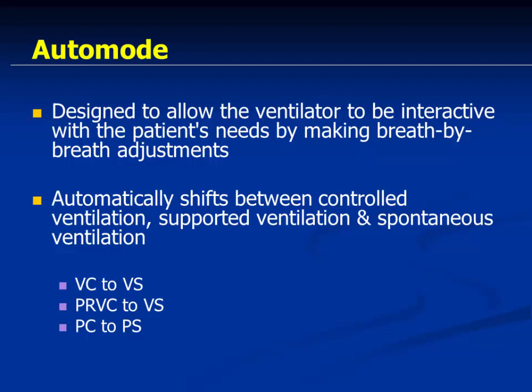You put the patient on control mode, start Auto mode, and next day morning you find that your patient is almost weaned. So it changes from volume control to volume support, pressure regulated volume control to volume support, pressure control to pressure support, and back and forth also. If the patient has apnea, not taking breaths, it will automatically go back to the previous mode.